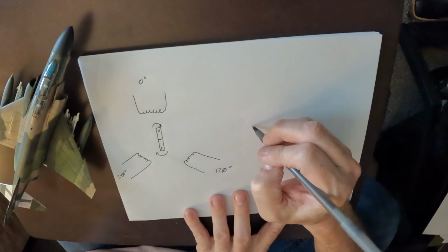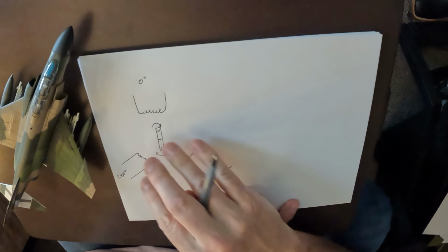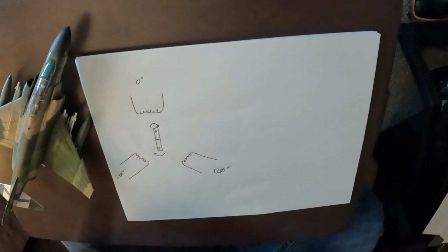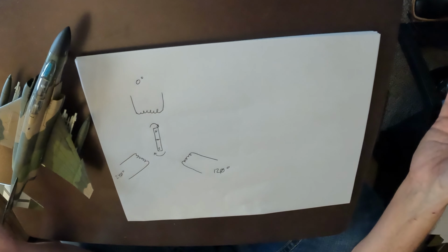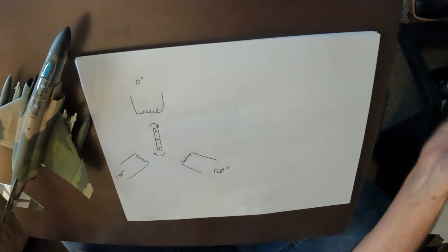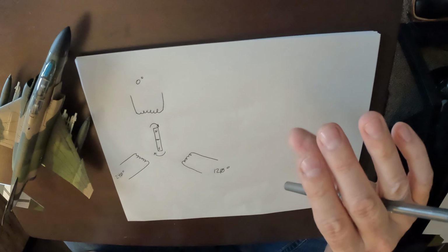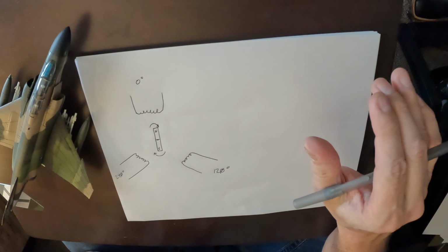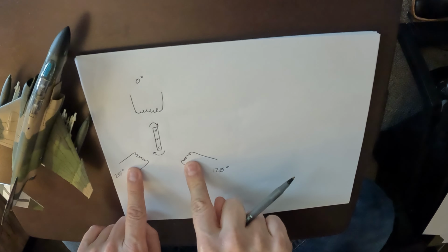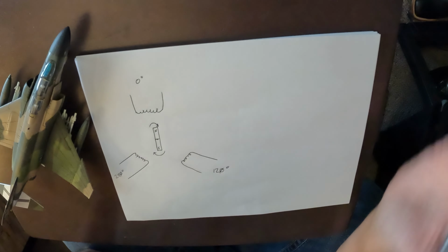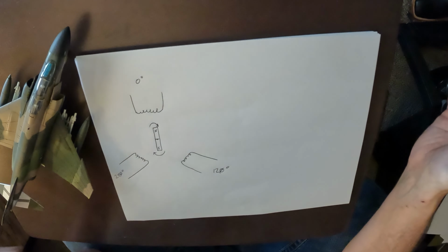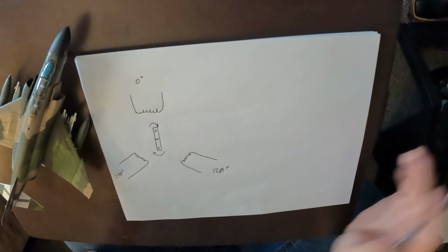The advantage of having a coil at the rotor is that if you put voltage into that coil, you create a magnetic field. You've created an electromagnet. And if you adjust the voltage in the rotor, you control the voltage on your stator coils, and that is the basis of a voltage regulator.